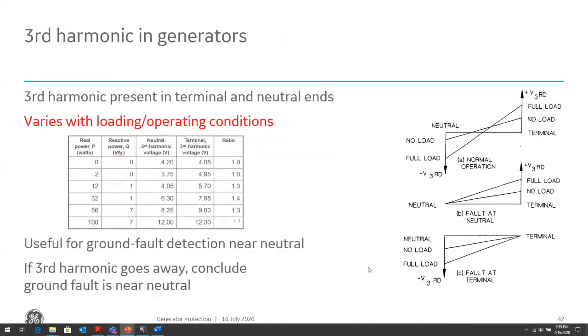The 27TN looks at third harmonic voltage, and why does it look at third harmonic voltage? It is the construction of the generator, the inaccuracies in the construction and the inaccuracies in the hookup of the generator, that cause third harmonic voltages to be generated while the generator is running. And we can make use of this phenomenon.